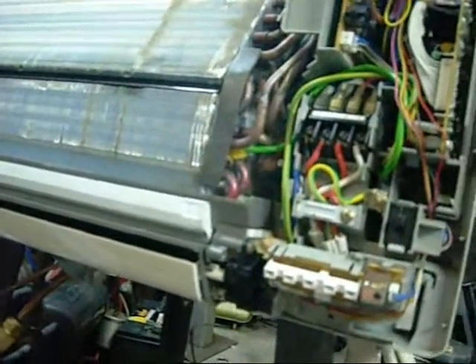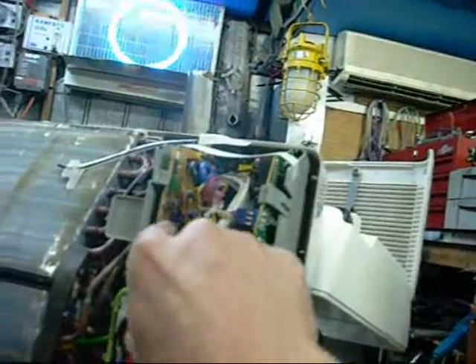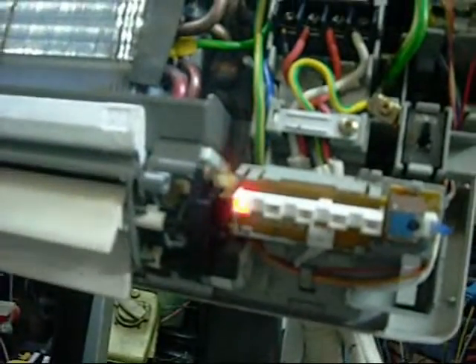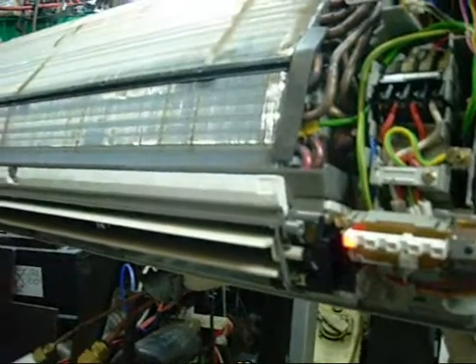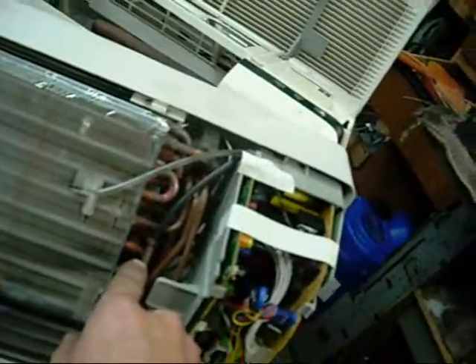Some of them lose their home position if you manually move the louvers. It's a bit hard to take the front panel off without manually opening them — you can't get to the screws. I don't know what this button does — it makes the red light flash. The fan is running again on low. It's probably waiting for a signal to heat up. This little sensor here tells it when the coil is hot and it goes into heat mode. I just heard a relay click and it stopped flashing.